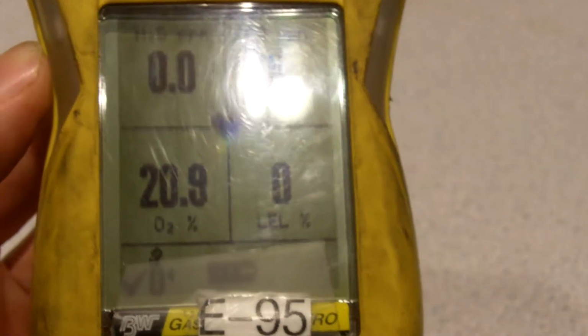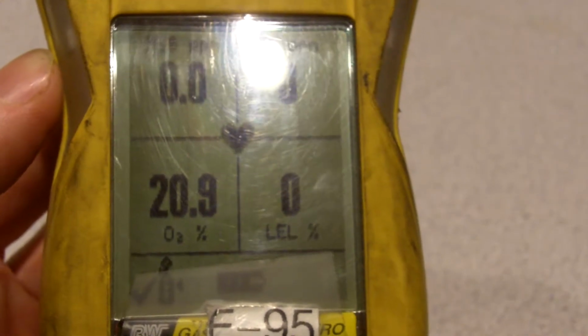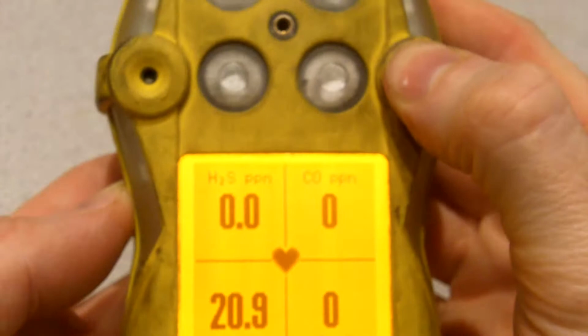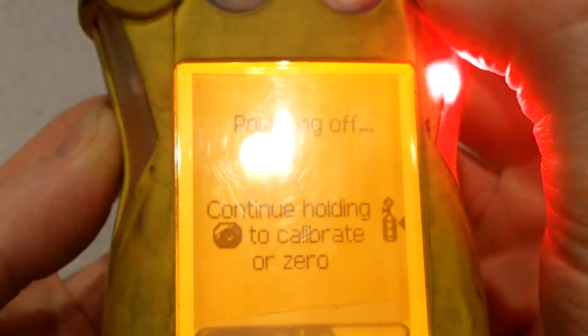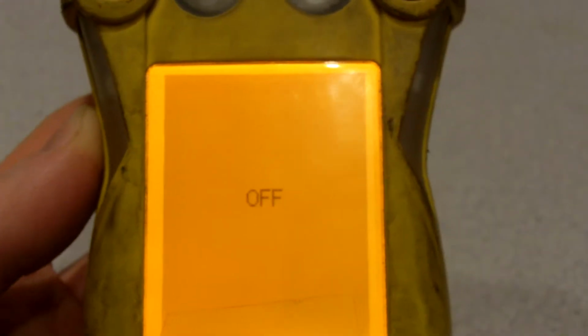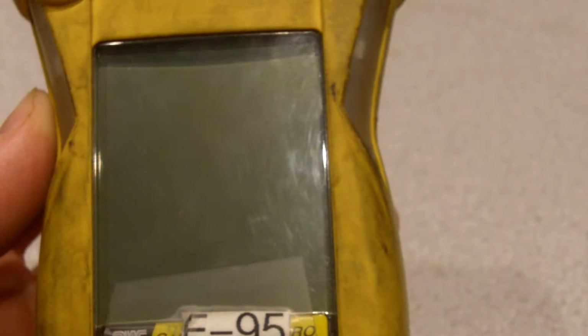So if I'm on scene, I'm right now using a rechargeable battery pack. Let me go ahead and turn this off. See, I'm going to hold the button. This is powering off. Continue to hold to calibrate. If I continue to hold, if I was your guys' gas monitor tech, I would be allowed to put it in the calibration mode to set those sensors back to whatever my testing gas is.